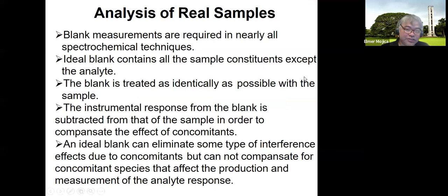And the one thing that you're going to do is what? Blank measurement, required in nearly all spectrochemical techniques. Can we consider blank as water? Is water the blank in all analysis? Is water always the blank? The answer is no. Okay? The definition of the blank is everything except the analyte. So an ideal blank contains all the sample constituents except the analyte.